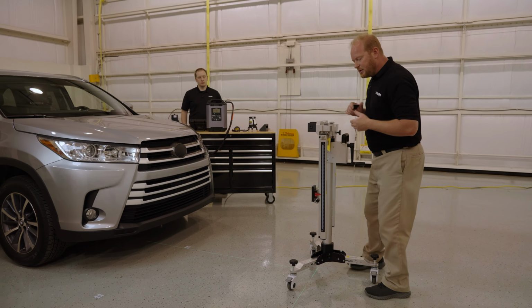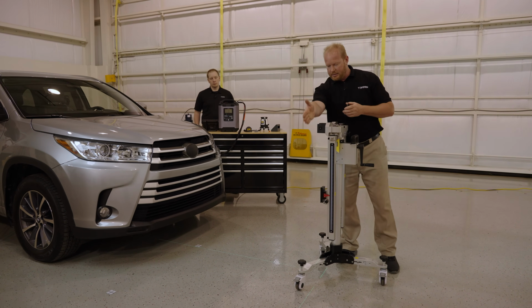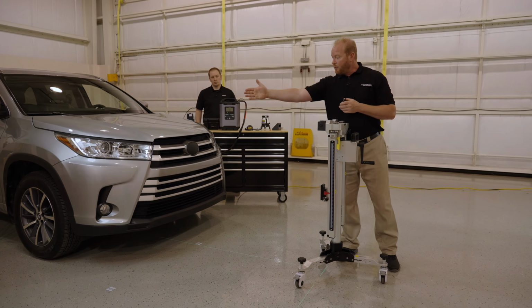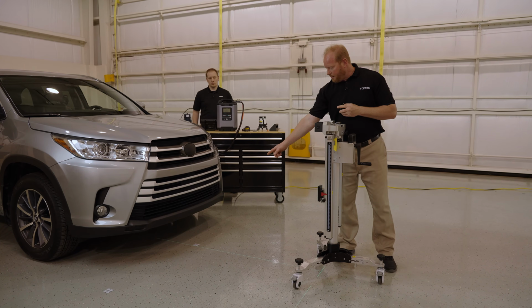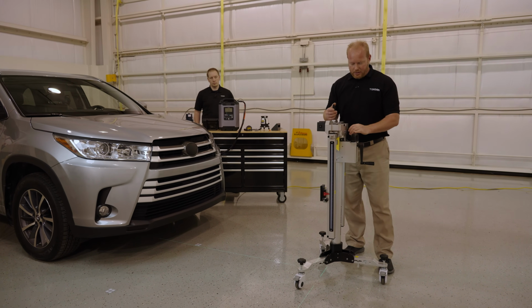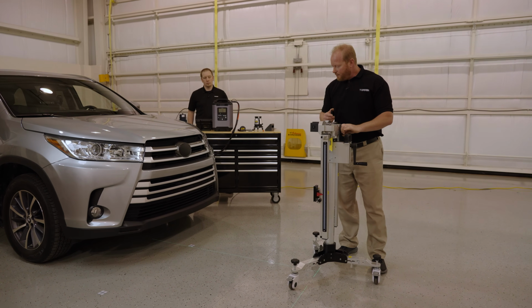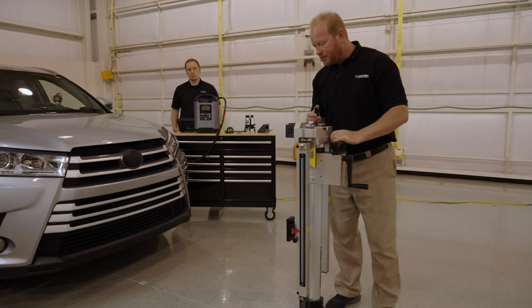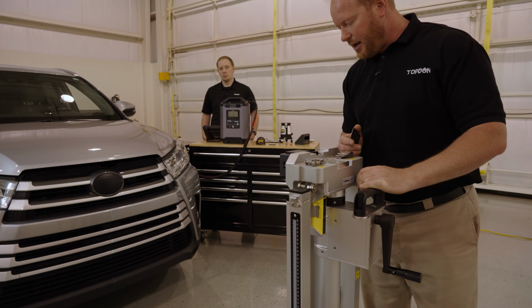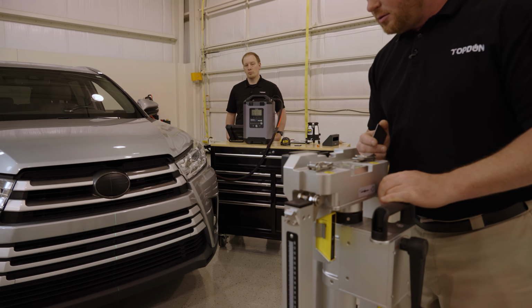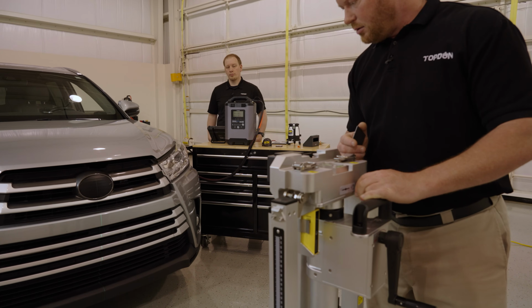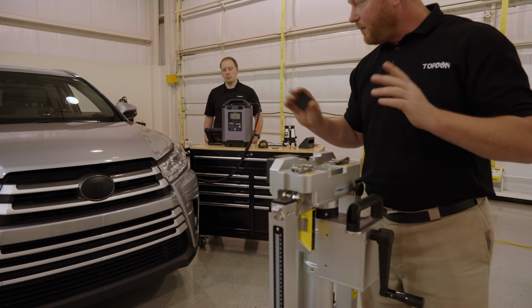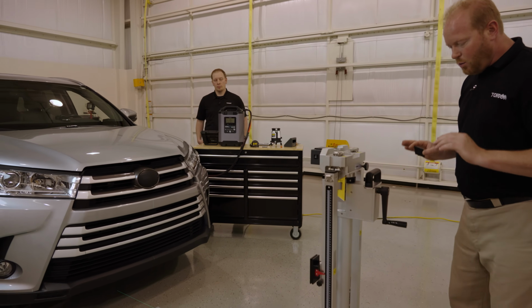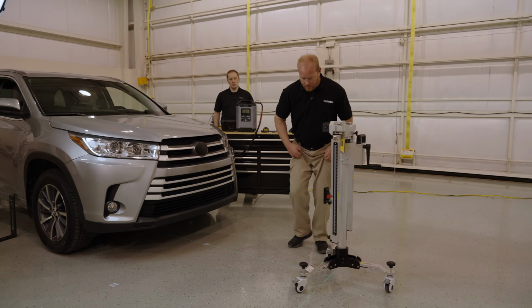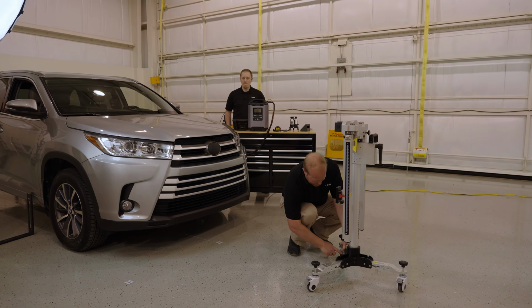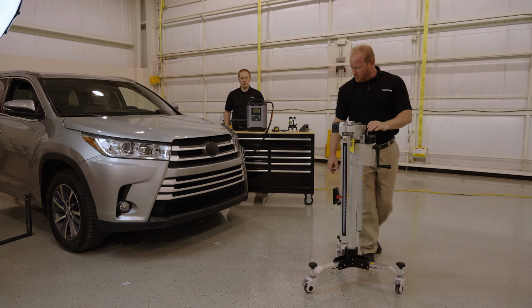And I don't know if you can see this on camera, but this laser goes forward and to the side. So now I can see that I am at my 3000 where I'm supposed to be from the camera, but I'm not precision on my marks for center line. So on the back of the calibration stand, there's a fine tuning knob, and we can fine tune that to get that perfect alignment. And we can get it very, very close with that knob. And there we are. So now that we have that perfect center line, I'm going to lock this guy down and get it to where it's going to live. We're going to do that with the little feet on the bottom here. Just push down on those. If I need to do a little bit of precision after that, I can always do that fine tuning again if we need to.